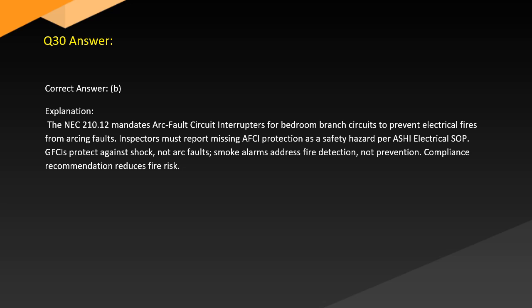Answer. Correct answer, B. Explanation. The NEC 210.12 mandates arc fault circuit interrupters for bedroom branch circuits to prevent electrical fires from arcing faults. Inspectors must report missing AFCI protection as a safety hazard per the ASHI electrical SOP. GFCIs protect against shock, not arc faults. Smoke alarms address fire detection, not prevention. Compliance recommendation reduces fire risk.